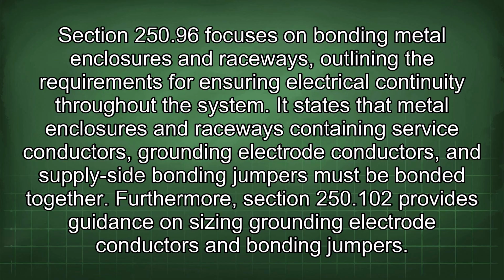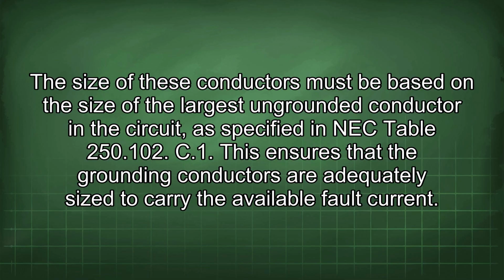bonded together. Furthermore, Section 250.102 provides guidance on sizing grounding electrode conductors and bonding jumpers. The size of these conductors must be based on the size of the largest ungrounded conductor in the circuit, as specified in NEC Table 250.102. This ensures that the grounding conductors are adequately sized to carry the available fault current.